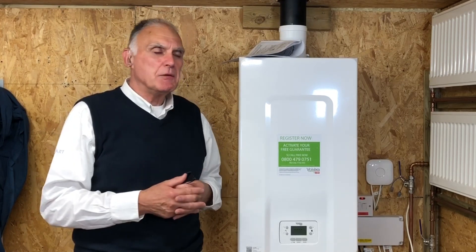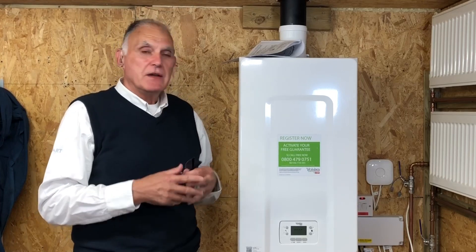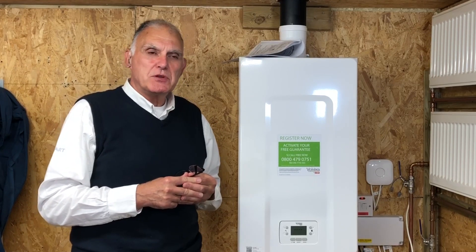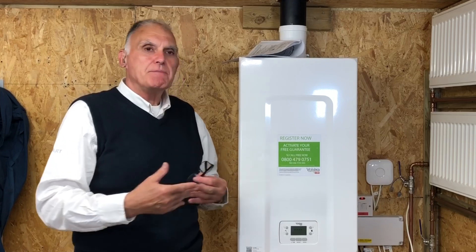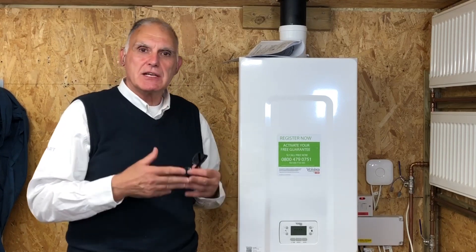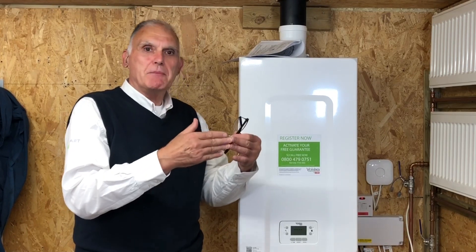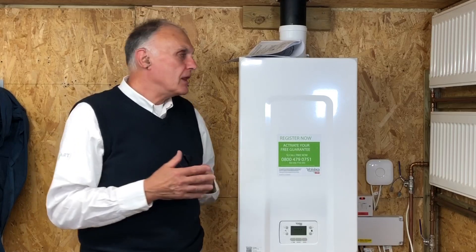What I'd like to talk about now is range rating. Combination boilers are very powerful - this particular one is 35 kilowatts and can put 30 kilowatts into a heating system. The average three-bedroom semi-detached house would need between six and ten kilowatts. So the boiler is more powerful than necessary. We can tune the boiler - we call it range rating - to the output that the house actually requires. If you let it run at 30 kilowatts, it will put so much heat into the house that the boiler will shut down, come back on, and shut down again. Cycling has a big effect on efficiency, so let's avoid it.